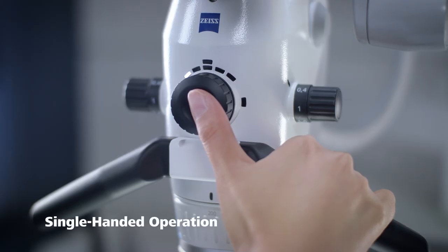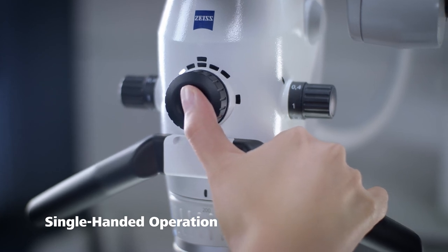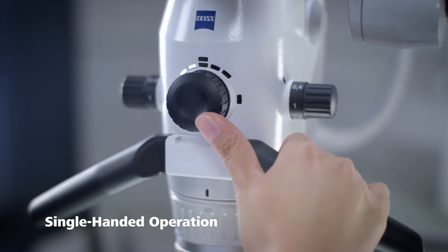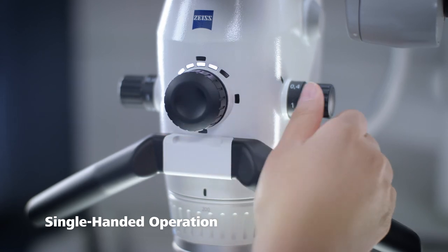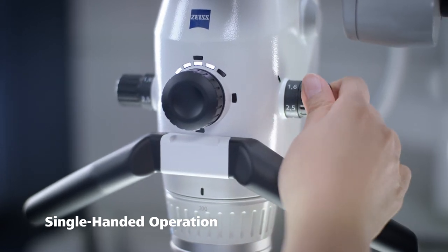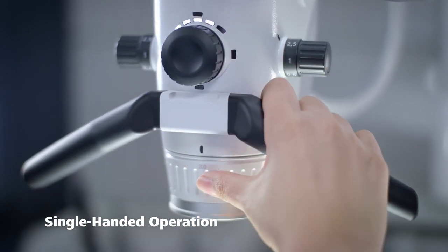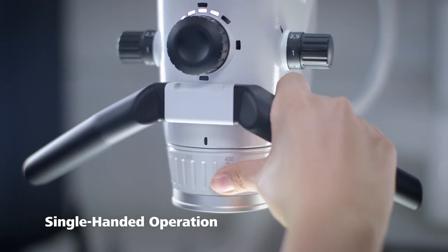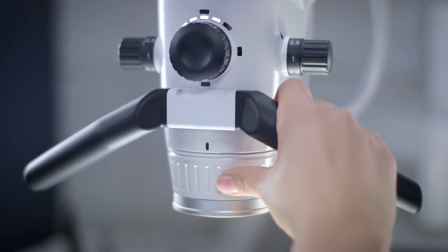The microscope body of the Zeiss Extaro 300 is designed so that you can reach the multi-functional mode control to activate all visualization and capture modes as well as the light settings with only one finger. From the same hand position you can adjust the magnification and change the working distance of between 200 and 430 mm with the VARIOSKOP 230, enabling an uninterrupted workflow during treatment in all situations.